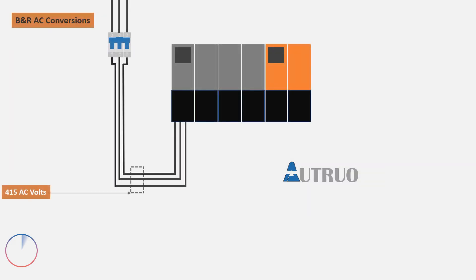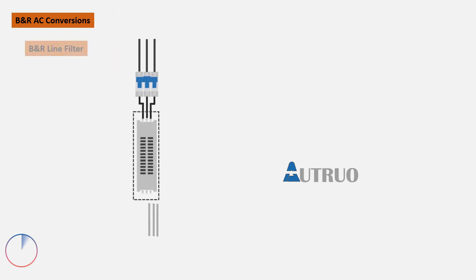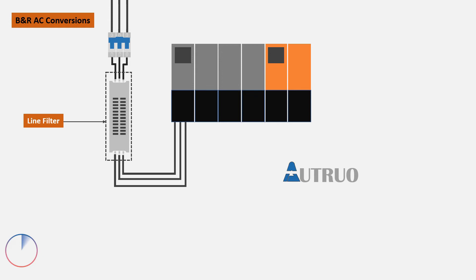The ACOPOS Power Module is powered by 415V alternating voltage. Before the power is connected to the power module drives, the incoming power will be connected to an electronic device known as a line filter. This filter is used to protect the drive against line interference, fluctuations, and harmonics, so the drive will be supplied with a steady power supply.